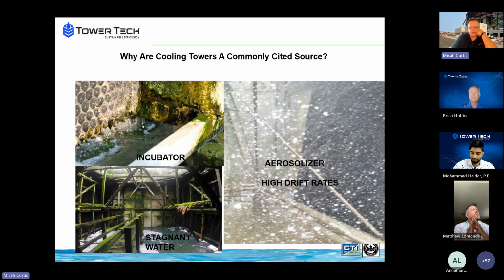Now, someone that looked at the picture on the bottom left, I would go, wow, that looks like a biodome for growing some algae, and looks pretty disgusting. But having been in, I don't want to say thousands, hundreds of cooling towers through the years, maybe over 1,000, I've often seen this same situation in field-erected towers and even package towers. You could almost say you have an ideal greenhouse to grow some algae, maybe get some Legionella bacteria growing in a cooling tower setup. Drift, on the right, certainly is something that we're going to talk a lot more about shortly. It's a big problem in the industry.